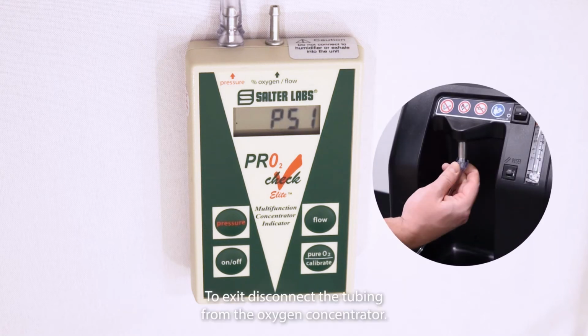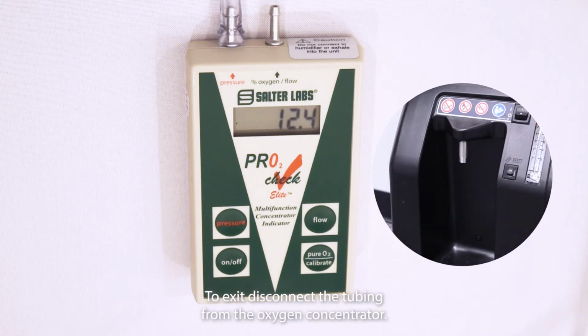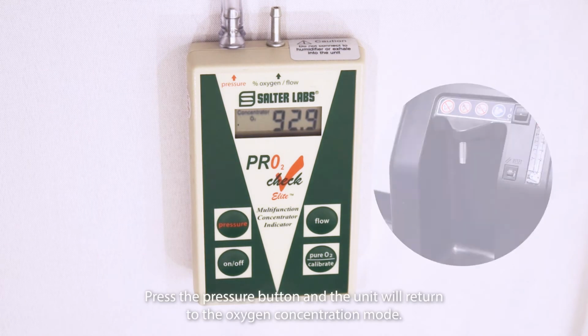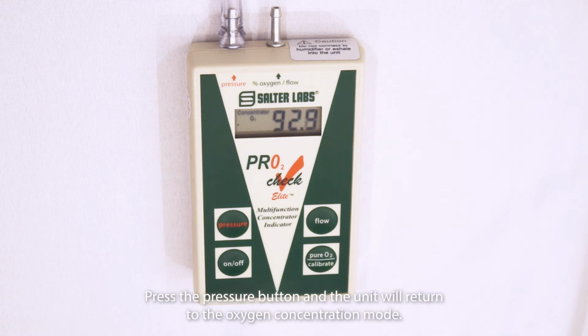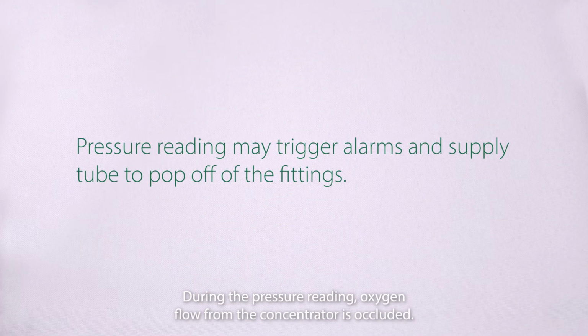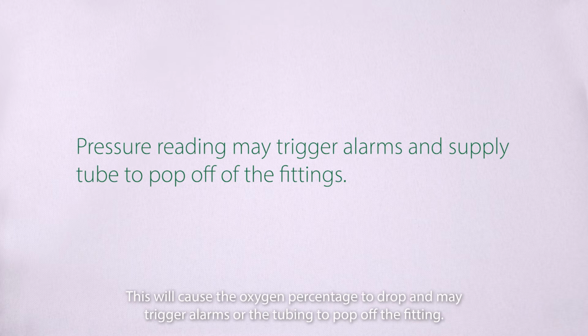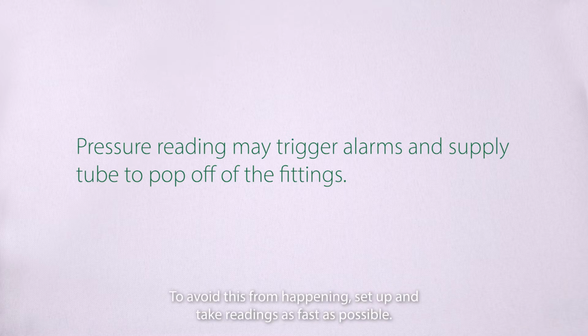To exit, disconnect the tubing from the oxygen concentrator. Press the Pressure button and the unit will return to the oxygen concentration mode. During the pressure reading, oxygen flow from the concentrator is occluded. This will cause the oxygen percentage to drop and may trigger alarms or the tubing to pop off the fitting. To avoid this from happening, set up and take readings as fast as possible.